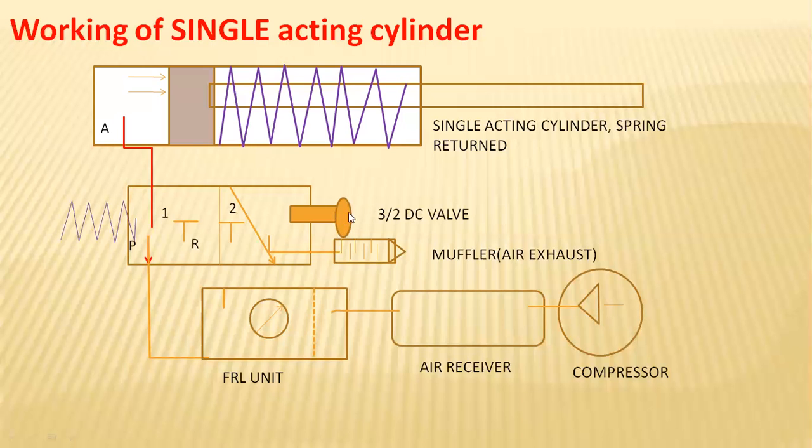So if the pressure has been released in the DCV, or the force applied on this push button has been released, nominally the spring will extend and the second position will change to the first position, and the compression created in the spring will be released, causing the return stroke of the piston, and the return air will be released towards the atmosphere.